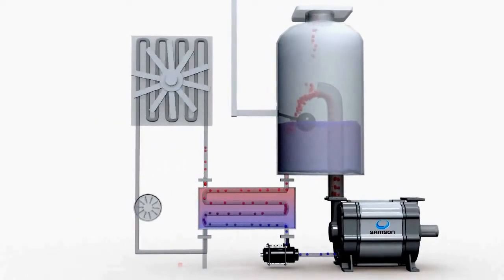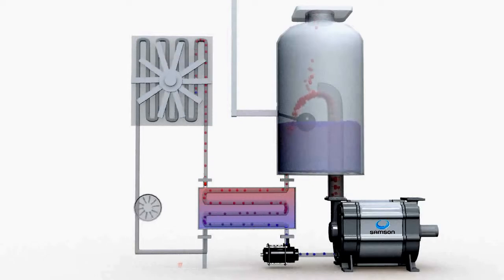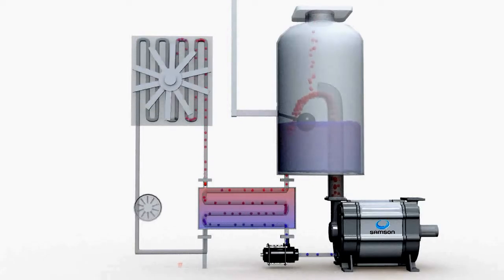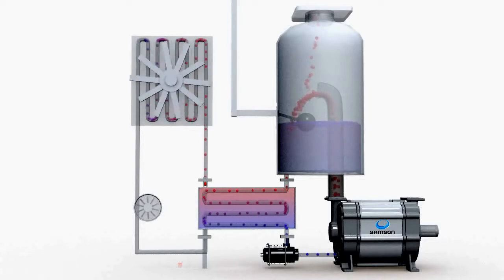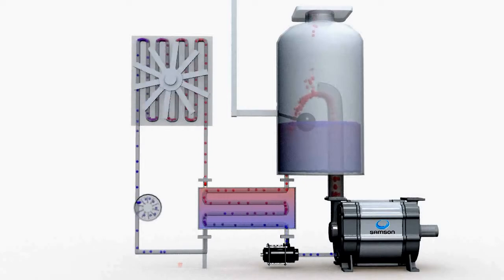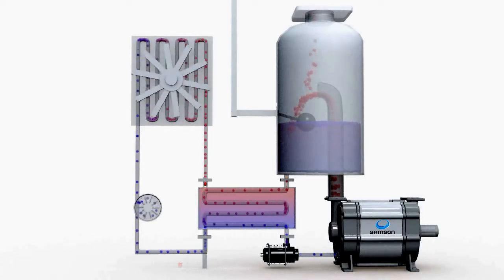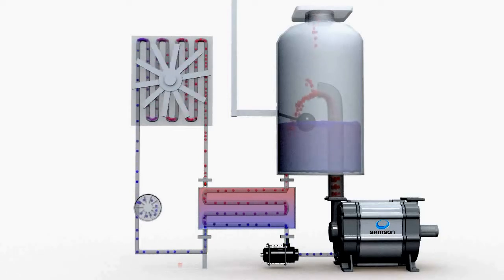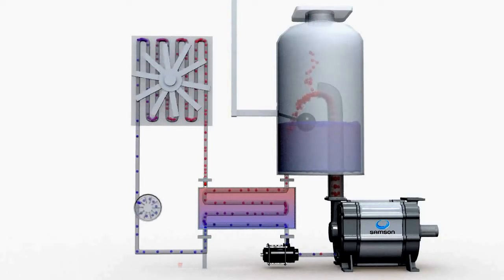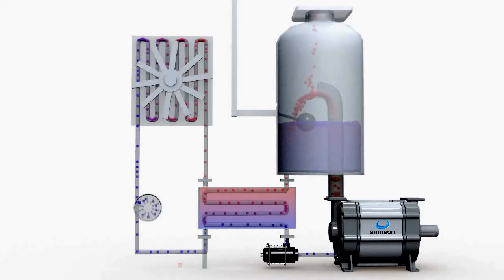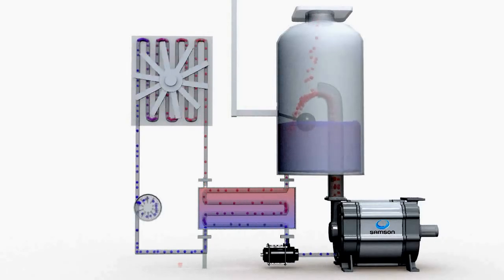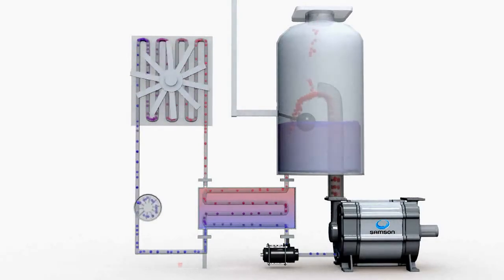To minimize water use, an air cooler can be added. The operating temperature is generally slightly higher than that of previous solutions, typically around 20 degrees centigrade above the ambient temperature. As the air cooler is sensitive to impurities, the unit includes two cooling circuits. The hot sealant liquid is fed through a heat exchanger, where it's cooled by the cold water from the air cooler. This means that any impurities drawn through the liquid ring vacuum pump will not be fed through the air cooler.